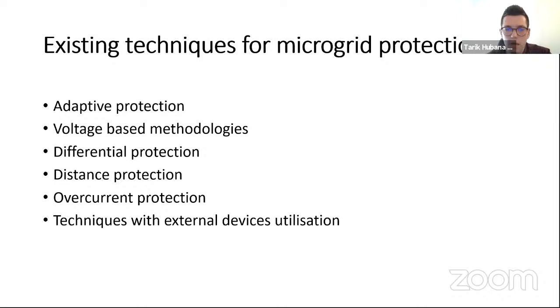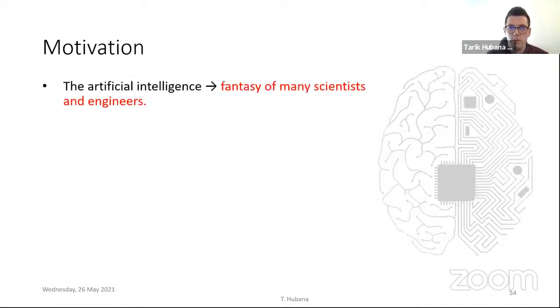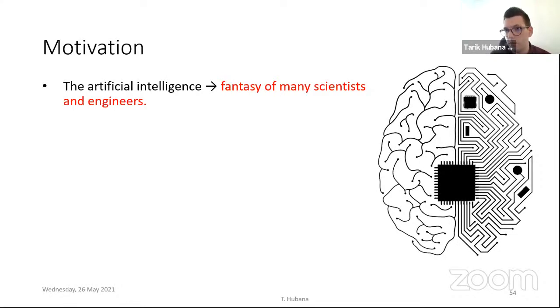Of course, all of these problems can be solved. We have the technology to solve these problems. We have the relays. We can protect the microgrid with the technology that we have today. Existing techniques that actually answer these previous problems are adaptive protection, voltage-based methodologies, differential protection, distance protection, overcurrent protection, and techniques with external devices utilization. However, all of these methods, although they can perfectly solve the problem, are just not feasible to be used on the low voltage or medium voltage levels. So these expensive relays are commonly used in the high voltage levels, where it is perfectly reasonable to use these devices. Therefore, this was the motivation for the next couple of researches that we were doing that are actually based on artificial intelligence.